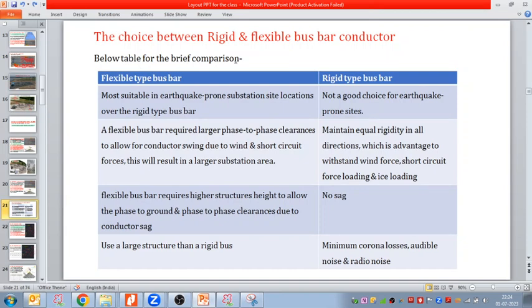The choice between the rigid and flexible bus bar conductor: flexible type bus bar is most suitable in earthquake prone substation site locations over the rigid type bus bar. Rigid type bus bar is not a good choice for earthquake prone areas. Flexible bus bar requires larger phase-to-phase clearances to allow conductor swinging due to wind and short circuit forces. This will result in larger substation areas. Rigid bus bar maintains equal rigidity in all directions, which is an advantage to withstand wind force, short circuit force, loading, and ice loading.